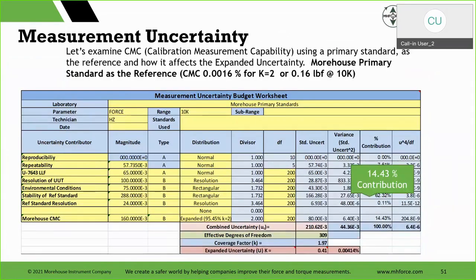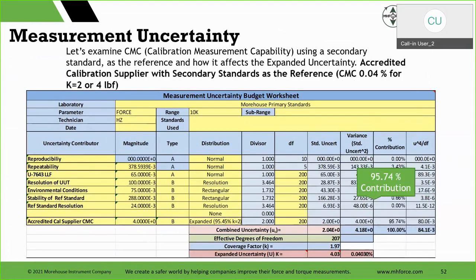If you look at this one here, you have a 14.43% contribution when using dead weights for your calibration. And if we look at the next one, where we use an accredited cal supplier, that's the next level down on the pyramid, we have a 95.74% contribution. So pretty drastic differences between the two.